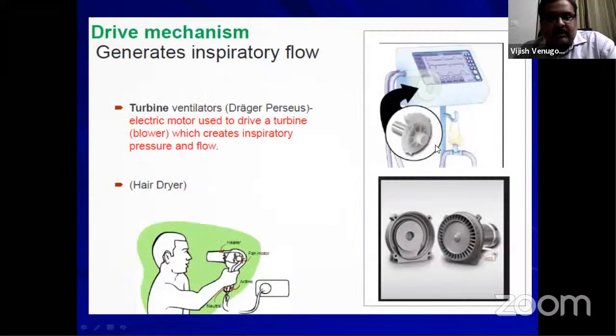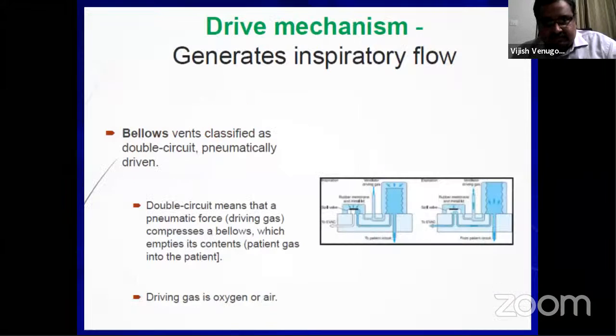The other one is the turbine ventilators. The turbine ventilator is an electric motor which is used to drive a blower which creates inspiratory flow and pressure. So this is a picture of a turbine. This is similar to your hair dryer, where you turn on the hair dryer and you get air blowing out. So the advantage of a piston and a turbine ventilator is that it does not require the presence of compressed gas.